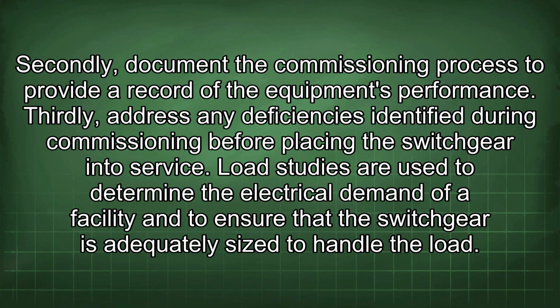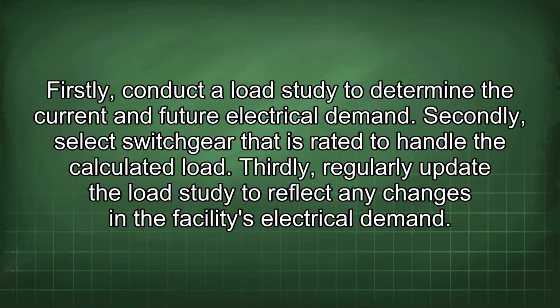Load studies are used to determine the electrical demand of a facility and to ensure that the switchgear is adequately sized to handle the load. Firstly, conduct a load study to determine the current and future electrical demand. Secondly, select switchgear that is rated to handle the calculated load. Thirdly, regularly update the load study to reflect any changes in the facility's electrical demand.